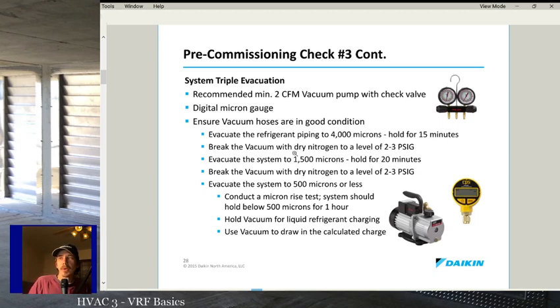So then break the vacuum with dry nitrogen to a level of 2 to 3 psi and let the nitrogen flow through the circuit and then out the other side. So you kind of want to purge the system with nitrogen at low pressure. You don't want to open it before the system's pressurized because you don't want to draw air in, but you want to purge the nitrogen in one line and out the other to try and just carry some of that moisture out.